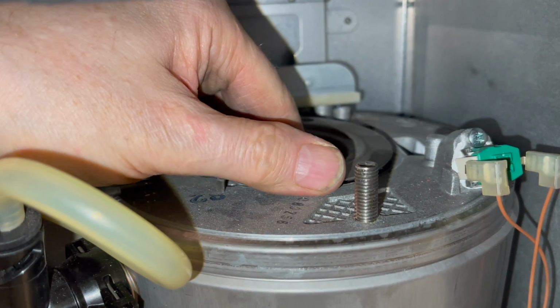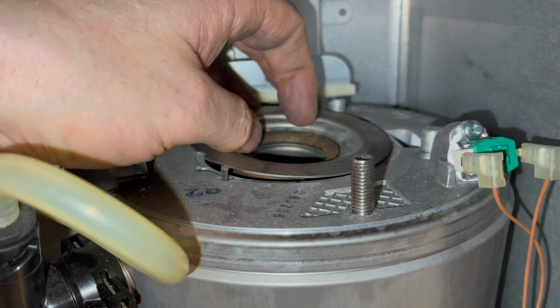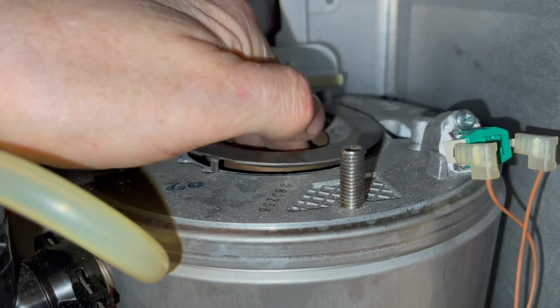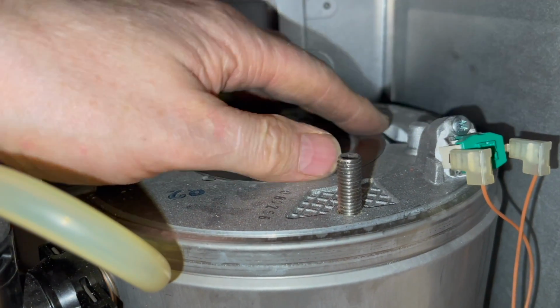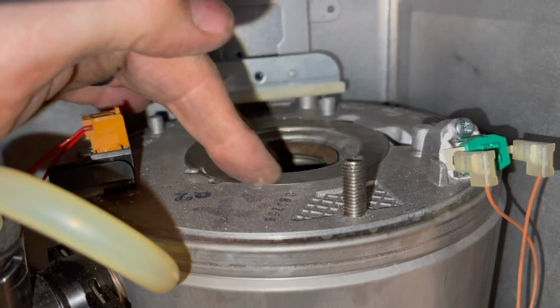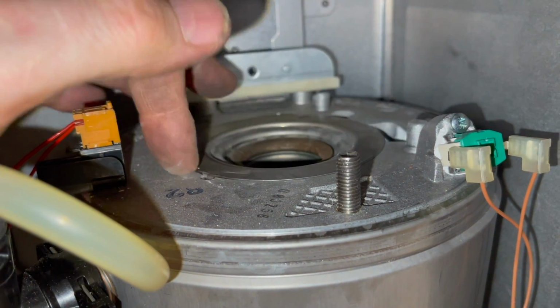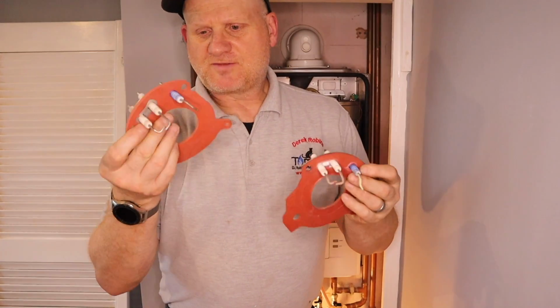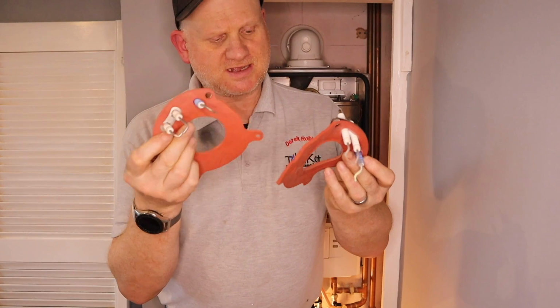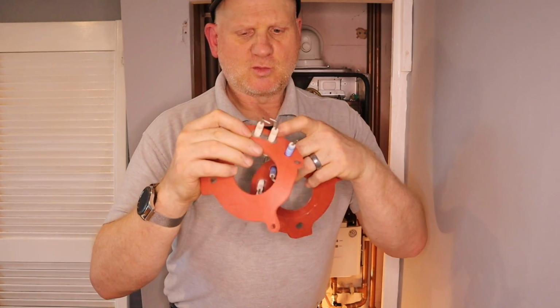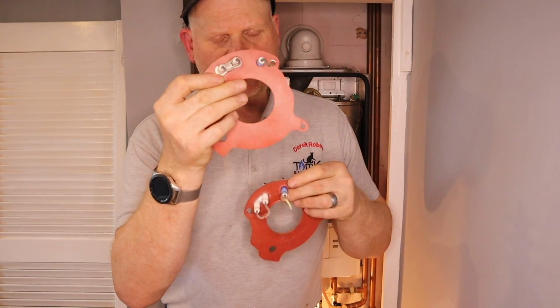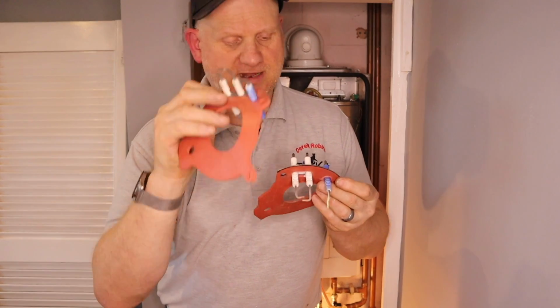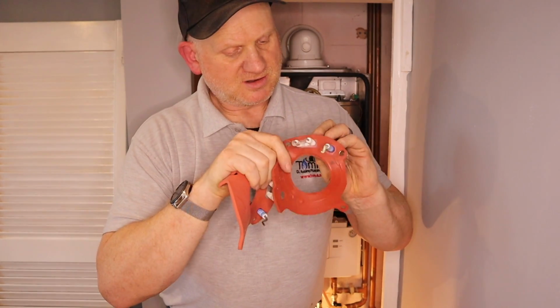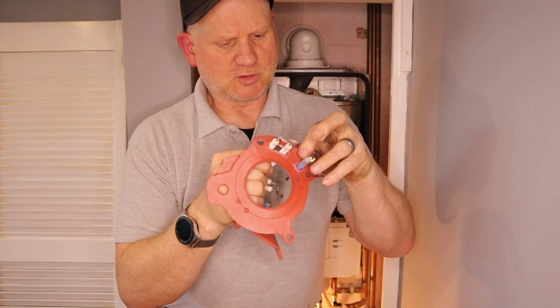So that's got in. So when you come to put the burner back in, the cup burner back in, it'll only go in one way, and it locates on these little pegs in the holes. So it stays flush like that. So they've slightly changed the gasket with the way the electrodes go through the gasket. So that's come already made up like that. But this one hasn't got this retaining clip on the bottom. So this is the old one.